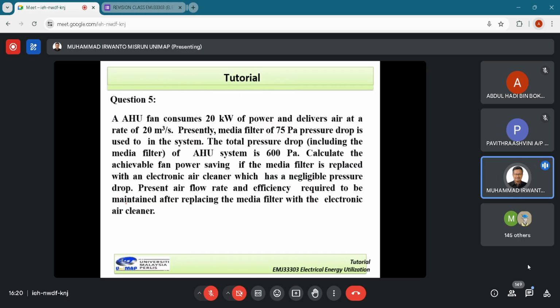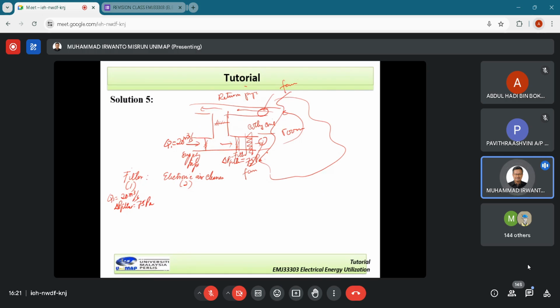Okay, and then the total pressure drop including the media filter, air handling unit system, is 600 Pa. This means this is still the first condition, delta P1 is equal to 600 Pa. This is for the filter condition, all of this.